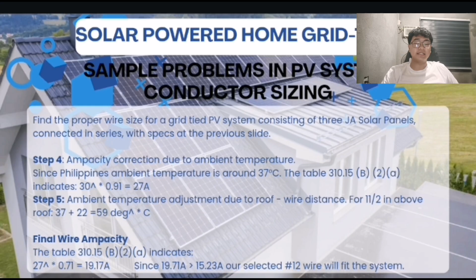So, makikita natin dito. Next naman ay step 3, refer on the table 310.15 B16 for the size of wire. So, the table indicates number 14 with ampacity of 25 ampere. Since number 14 is not the best practice for PV system, use number 12 with ampacity of 30 ampere. Step 4, ampacity correction due to ambient temperature. So, since the Philippines ambient temperature is around 37 Celsius, the table 310.15 B2A indicates 30 times 0.91 is equal to 27 ampere.